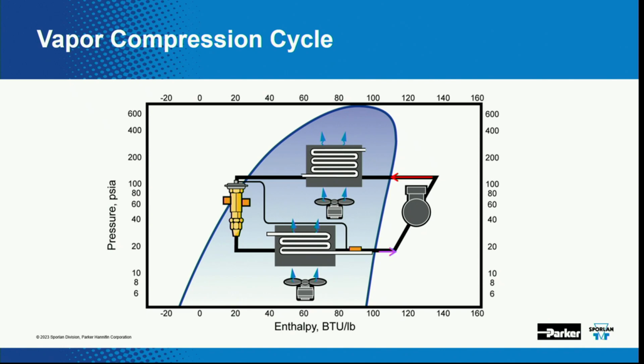Here are those components in the system superimposed now onto that trapezoid, so it's depicting exactly what's going on at those various stages. The thing to note is that the compression is always taking place in the superheated or the vapor side. Remember, all of this over here is vapor. The condensing and the evaporating are all taking place underneath the saturation dome. And there's a little bit of liquid in the system between the condenser and the expansion valve.